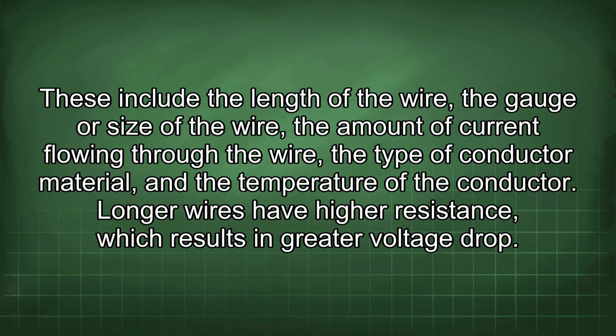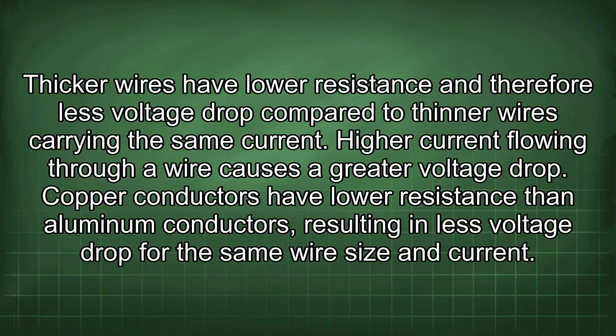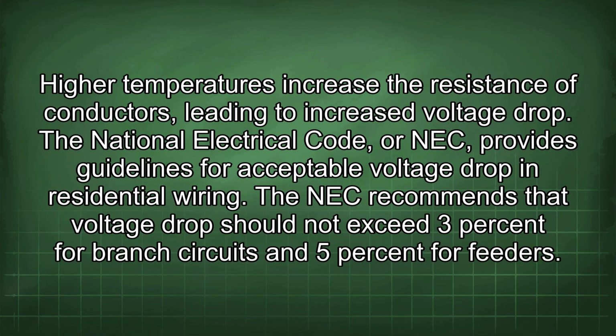Longer wires have higher resistance, which results in greater voltage drop. Thicker wires have lower resistance and therefore less voltage drop compared to thinner wires carrying the same current. Higher current flowing through a wire causes a greater voltage drop. Copper conductors have lower resistance than aluminum conductors, resulting in less voltage drop for the same wire size and current. Higher temperatures increase the resistance of conductors, leading to increased voltage drop.